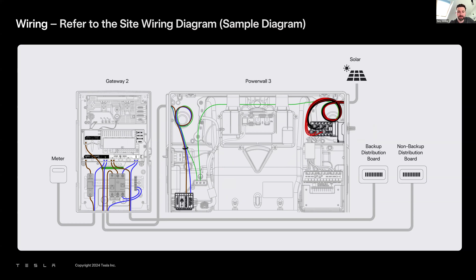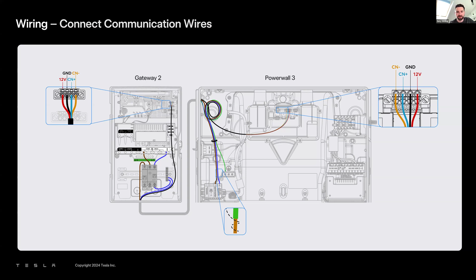From a communication perspective, you need to run comms cable from the gateway to the Powerwall. That's nothing new - anyone who's done Powerwall 2 in the past will know this. The only thing I want to point out here is the comms cable in the gateway is the reverse of what's inside the Powerwall. Inside the gateway, it goes 12 volt, ground, CAN high, CAN low. Inside the Powerwall, it goes CAN low, CAN high, ground, and 12 volt. It's stamped on the board, so it should be easy to follow. However, we like to point it out because people will just assume it's a mirror image of each other when it's not, so please keep that in mind when you're on site.